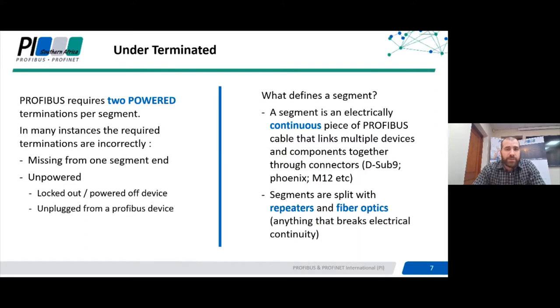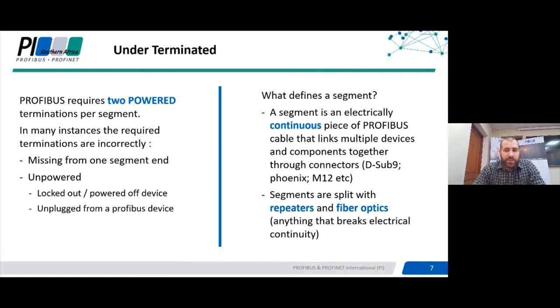A segment is an electrically continuous piece of Profibus cable that links multiple devices and components together through connectors. Segments are split with the use of repeaters and fiber optics. A given Profibus network would consist of multiple different segments because you have about 125 device addresses in a single network, and segments have limitations on total number of devices, total distance, split again with repeaters and fiber optic modules. On every single segment you must have two terminations — one at the beginning and one at the end. In many instances within industry these required terminations are either disabled or missing from either or both ends.